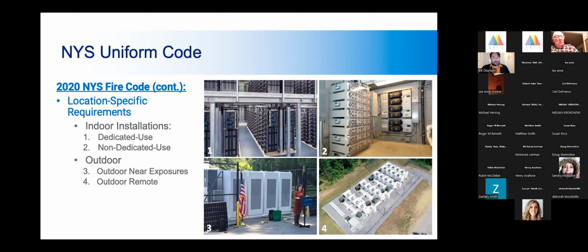We also have two types of outdoor installations. Outdoor near exposures means there's basically anything combustible within 100 feet of the energy storage installation. Outdoor remote means there is nothing combustible within 100 feet of the installation. So pretty simple. Dedicated use building is dedicated to the use of energy storage. Non-dedicated use building is a building that has energy storage in it and anything else going on. Outdoor near exposures is anything within 100 feet of the battery, and outdoor remote is nothing within 100 feet of the battery.